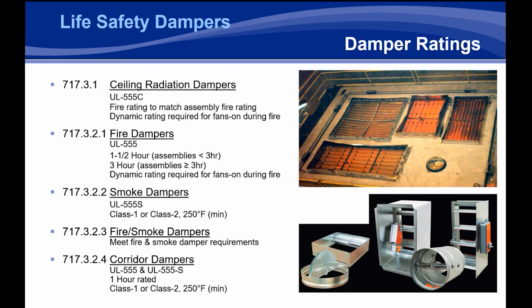Now, for a long time, there was no way, even when that code change was put in place, to be able to certify a dynamically rated ceiling radiation damper. And honestly, today, there's still no clear-cut way with, say, UL, Underwriters Laboratories, who certify most of these life safety dampers, to rate a damper dynamically. We're actually working with AMCA, the Air Movement Control Association is actually working with UL to change those standards to put language in to uniformly test dynamically rated sealing radiation dampers.